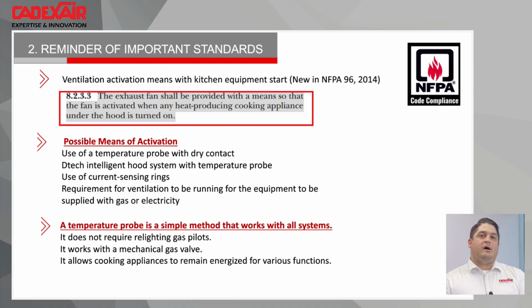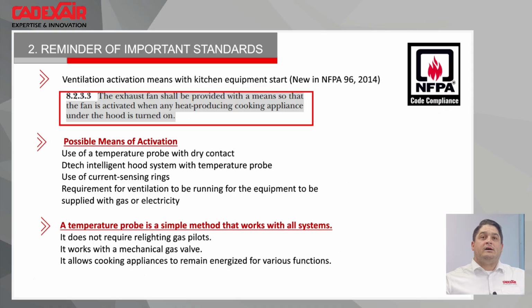The first one they added is that you now need to interlock the kitchen equipment with the exhaust. Technically, as soon as you start cooking, you need the exhaust to turn on. There are multiple means of activation. We can use a temperature probe with a dry contact, like a high limit switch on the top of the hood. As soon as it detects, because it's our demand control system, normally demand control systems have a temperature probe, so they can also start the system with a set point. We can use a current sensing ring on the cooking appliance. Or we can interlock the cooking appliance, so you need to start the ventilation to give power to the cooking appliance, or the gas. In many years we also had a lot of these demand systems. It was not as per code, but they don't want to start something before the others.